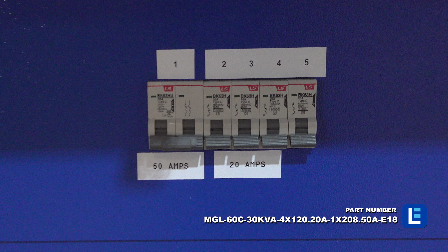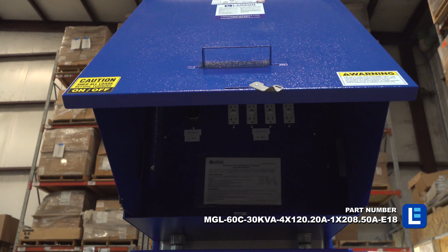120 and 208 volt line out protection is provided by 4 20 amp single pole breakers and one 50 amp 2-pole breaker. Connection for 208 and 120 volt AC is through receptacles mounted on the side of the load center. Receptacles include 4 20 amp 120 volt GFCI waterproof duplex receptacles and one 50 amp 208 volt receptacle.